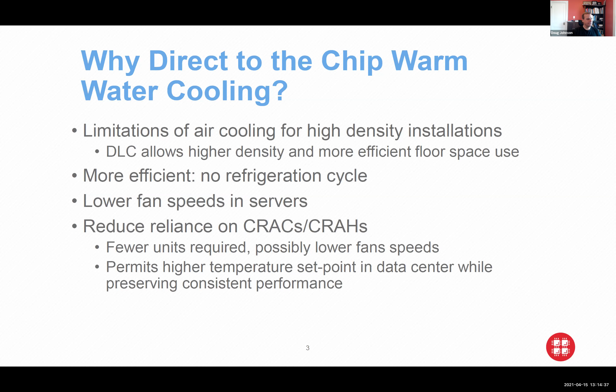There are some other benefits that are kind of second order. If you have direct to the chip cooling, you can have lower fan speeds in the servers, and I'll go over some of the numbers we've seen as a result of that. And if you're cooling with water directly to the chip, you can also have a higher set point in your server room. The equipment we have today is rated for much higher temperatures than the 18 degrees Celsius that seemed to be a pretty standard set point for server rooms in the past. There's no longer that much of a need to keep it like a meat locker.